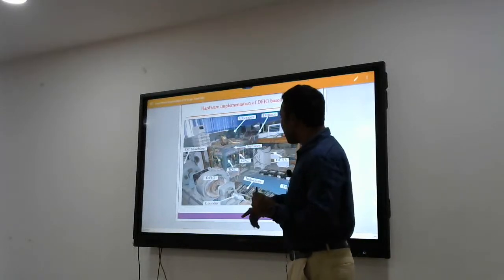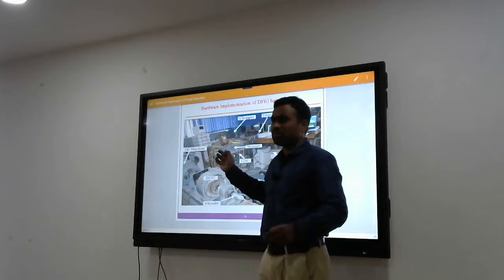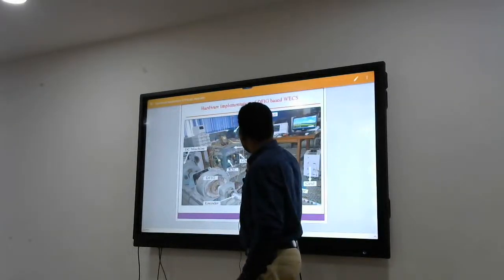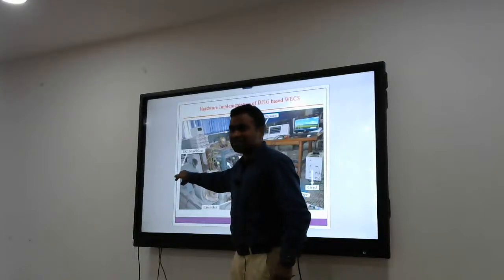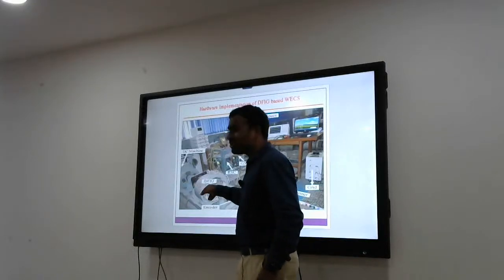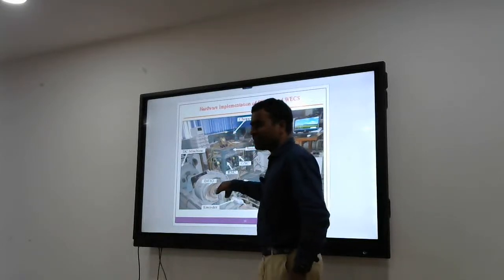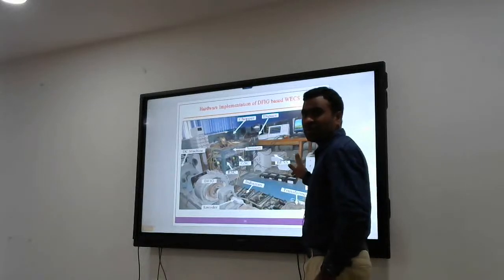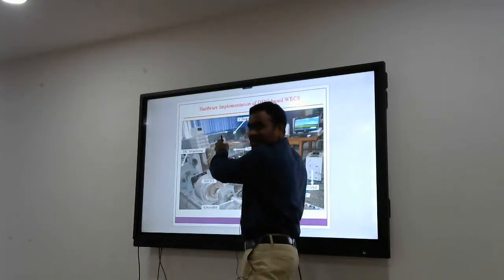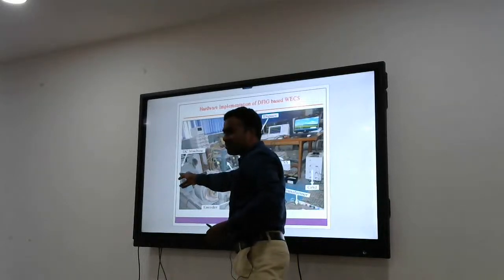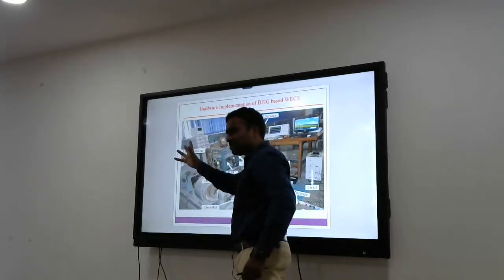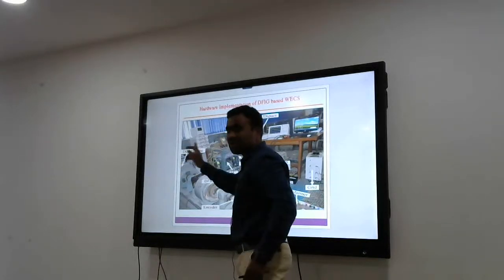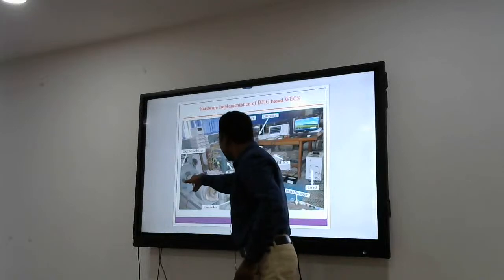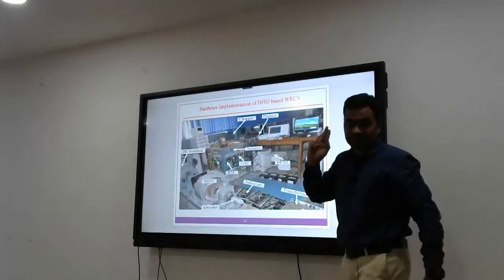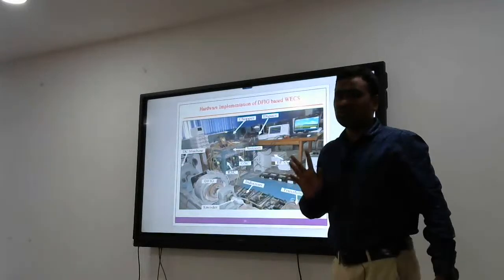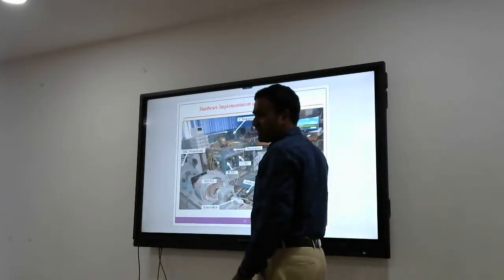Even if you see here, we have taken power from the grid only, from the grid through this auto transformer. It was given to the DC machine. This DC machine was coupled to the DFIG. It will convert mechanical energy to electrical energy. It will be fed back to this other auto transformer. It means the power was taken from the same grid and converted from electrical to mechanical in this DC machine. Also, with the help of this chopper, we have emulated wind turbine characteristics, and this mechanical energy was converted to electrical energy and fed back to the grid again. I think I have done around 3.7 kilowatt. I am able to send that to the grid.